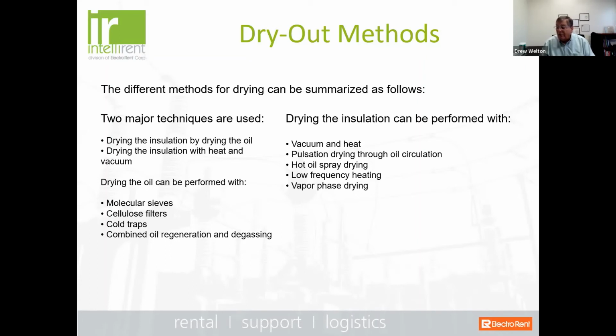We'll do a hot oil spray to try and pull that moisture out of the insulation. But again, the effectiveness and the cost of doing this: you have to have the transformer offline during this process, and that's a problem for a lot of utilities. And it's not all that expensive, all that effective, or not as effective as we'd like the drying process to be.